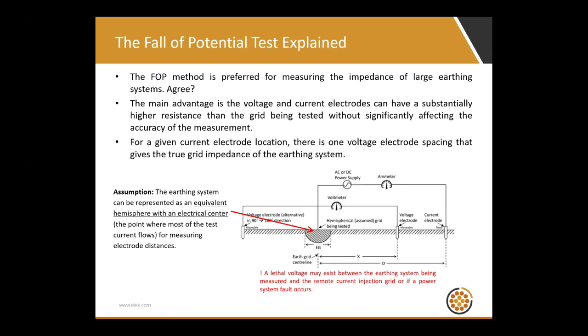A couple of assumptions are outlined here. An assumption is that the field formed by the grid is an equivalent or ideal hemisphere in the soil. That's very often not the case. Earthing systems are rarely symmetrical, and therefore the fields they form in the soil are almost never ideal hemispheres. And there are safety concerns with performing this test that you should consider. Lethal voltages can occur.